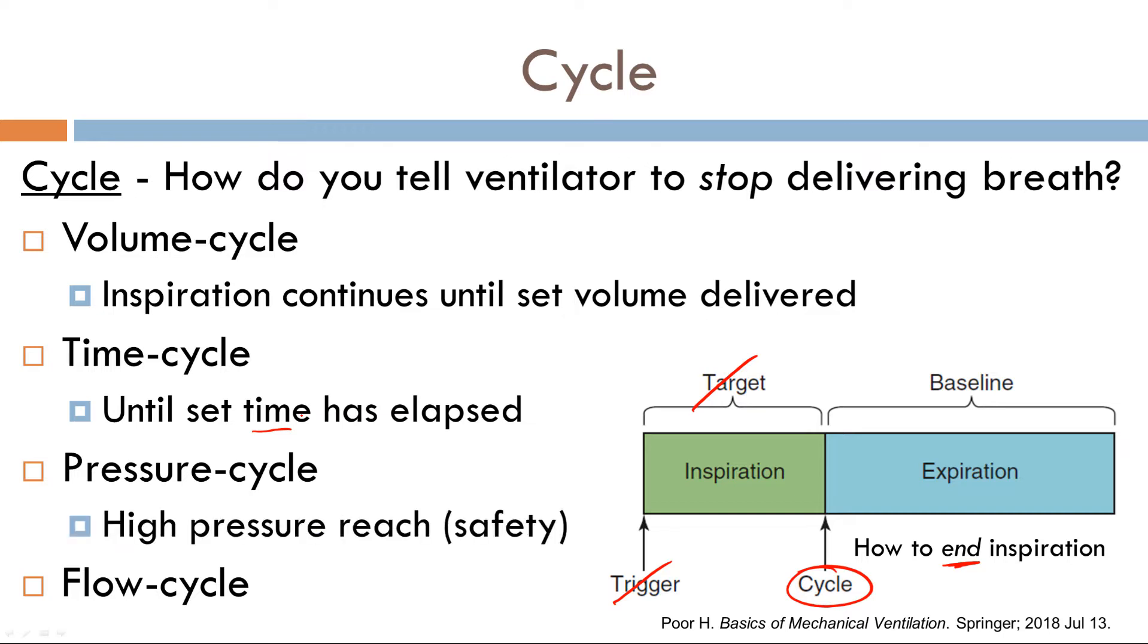What about pressure cycle? In pressure cycle, you set a pressure cycle, which is usually a backup safety mechanism. Once the pressure exceeds 60 centimeters of water, boom, stops delivering your breath. Why continue to deliver a breath if the pressure is exceeding so high above 60? So it's a safety mechanism. You use that to save yourself from possible barotrauma.